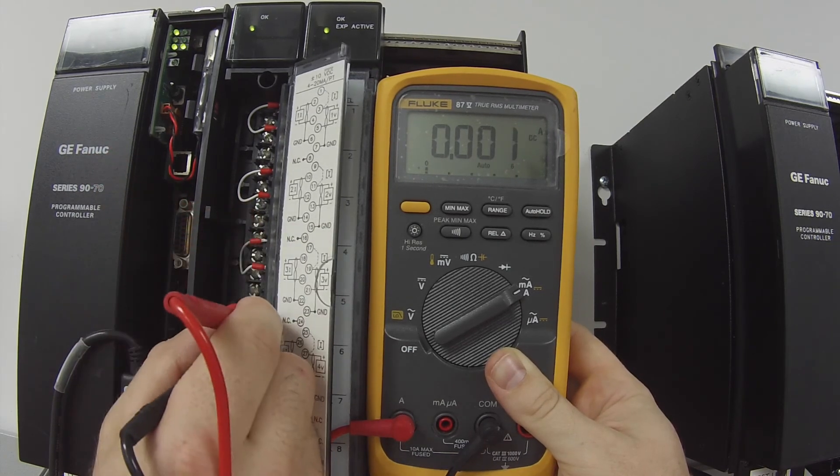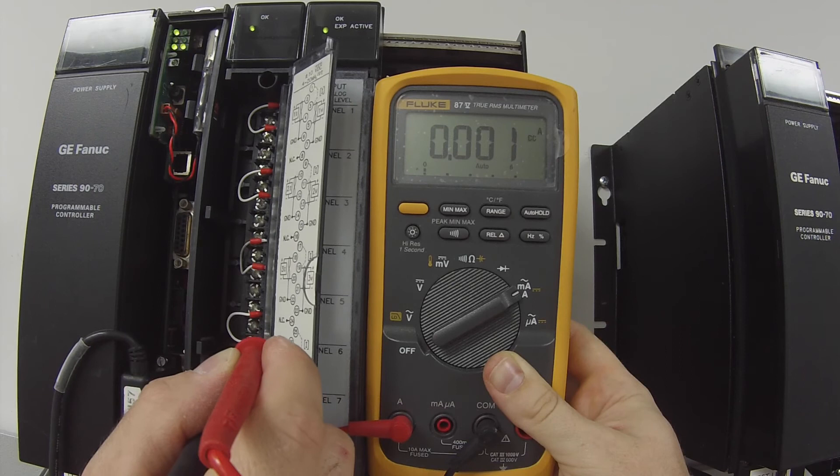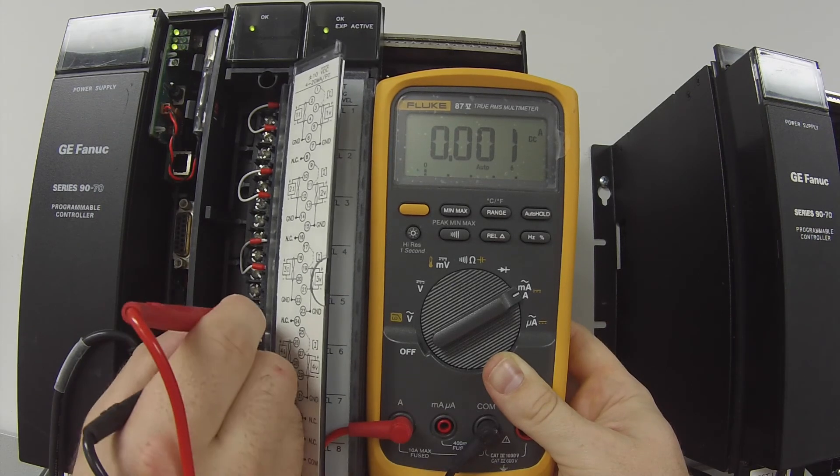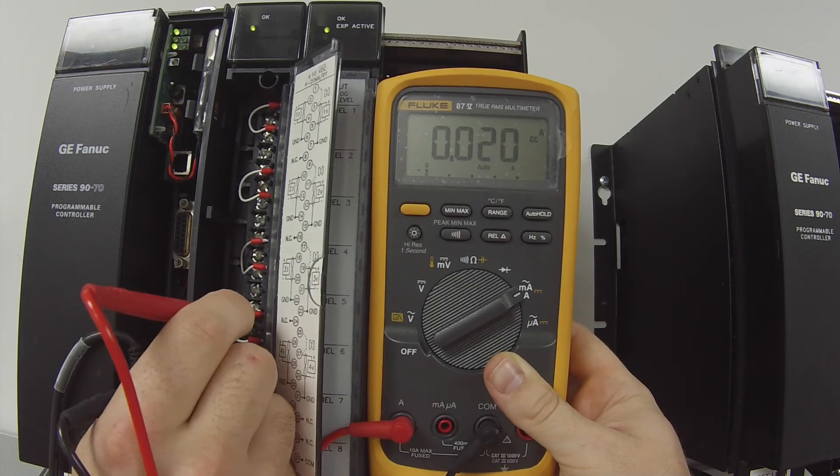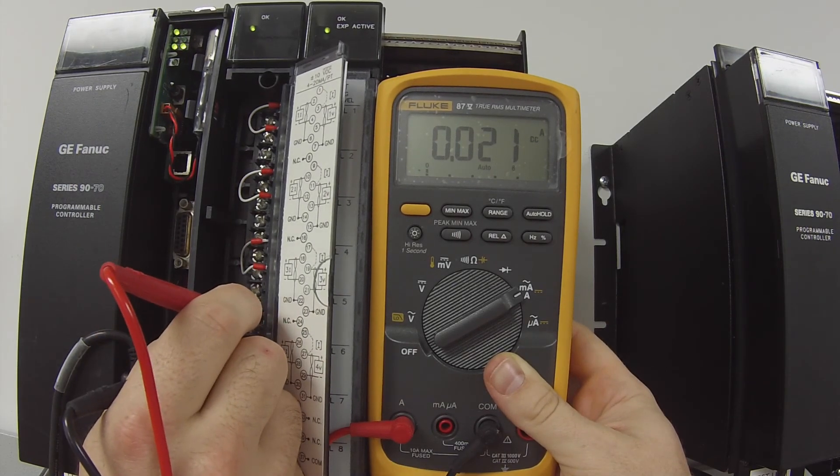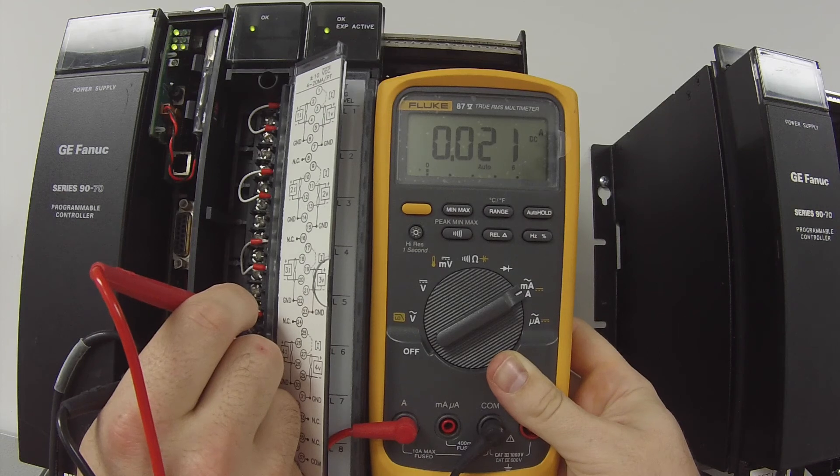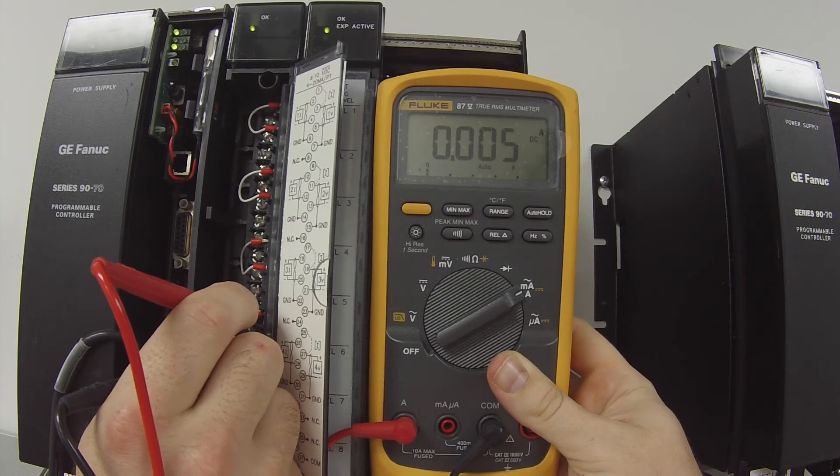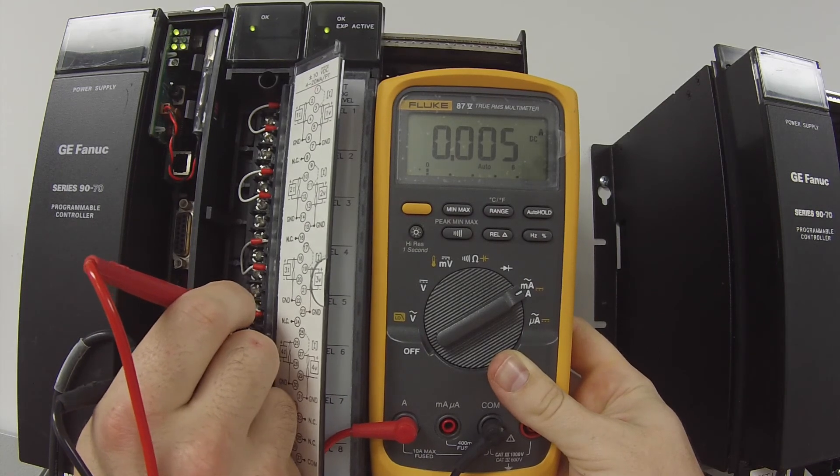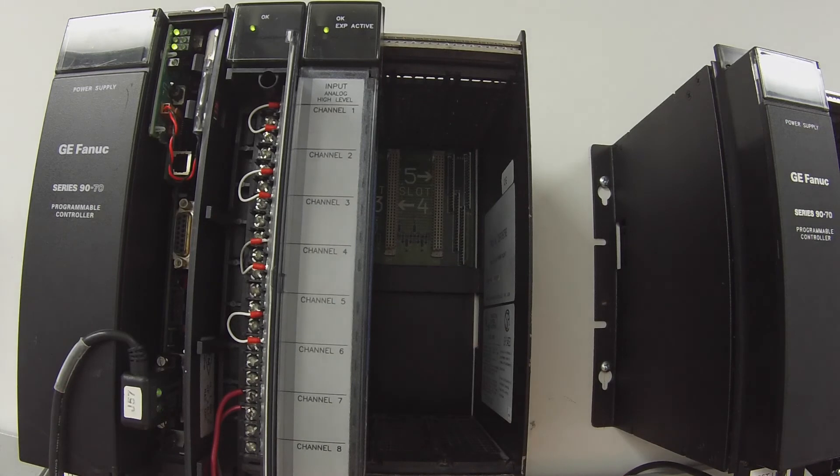The last one is number 4, terminals 26 and 28, 21 milliamp. We're going to drop it to zero. And it dropped. So everything's fine with that one. That's what you should expect to see.